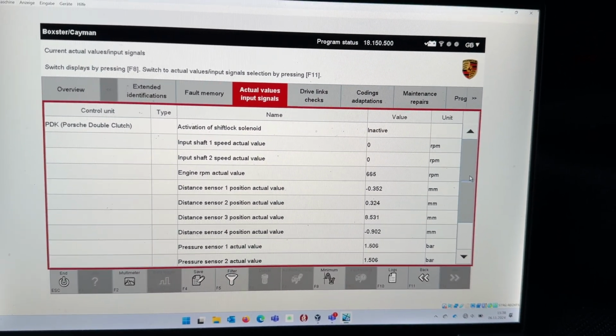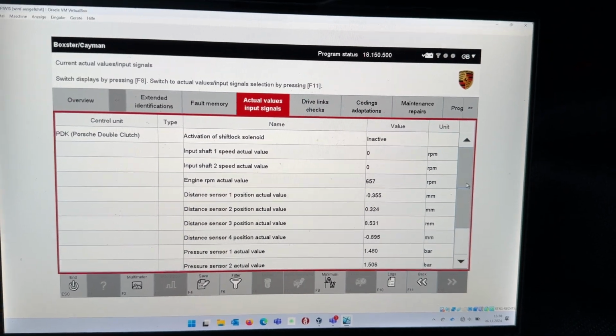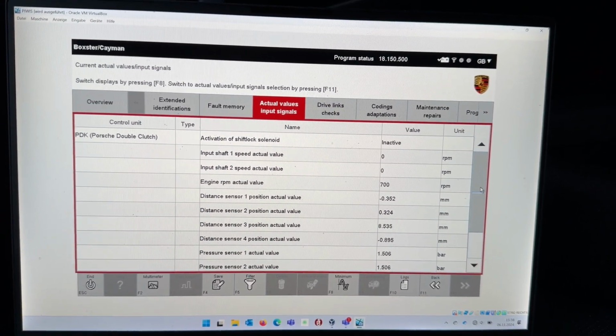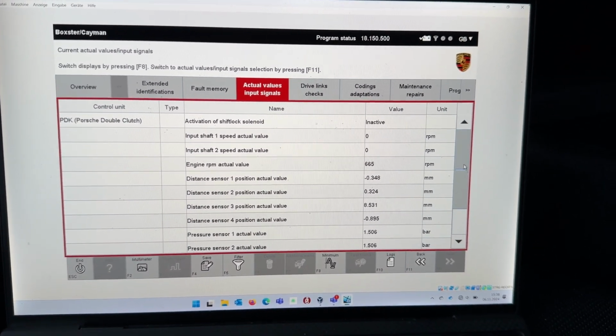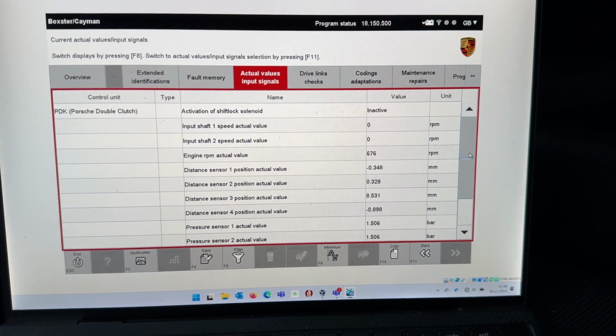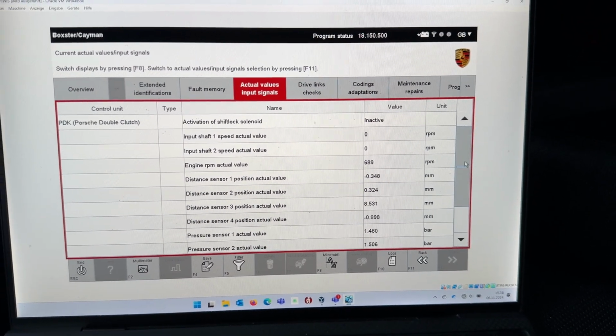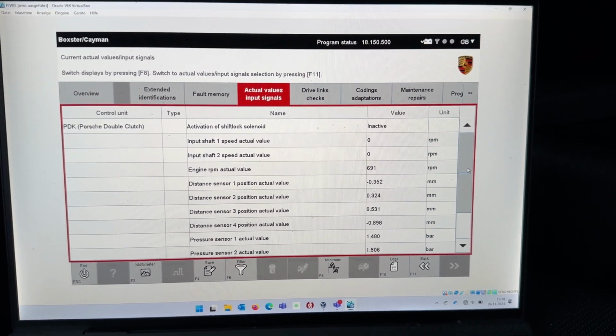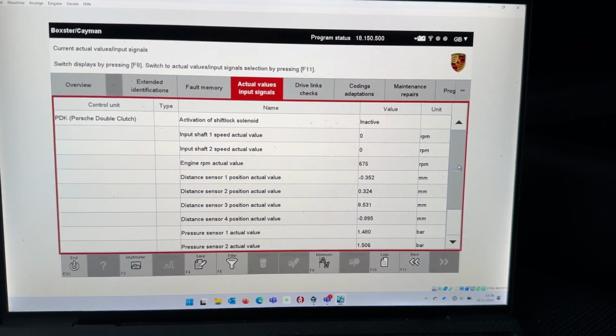We'll try to get something in gear, but as it actually measured something, that means irrespective of the error codes, which I would expect, it should be measuring something, because this is a measurement and it shouldn't prohibit a measurement if there's an error code active.